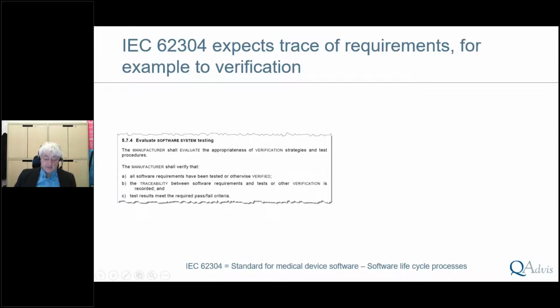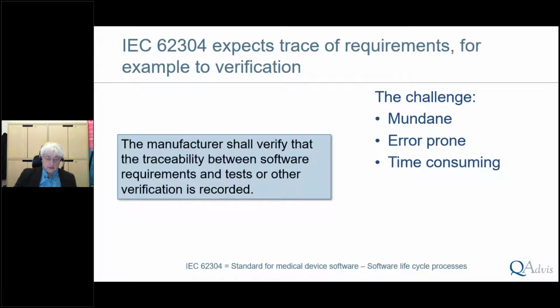The same expectations appear on software level and are elaborated on in the standard IEC 62304, of which you now see a screenshot. If we simplify the standard's text a little bit, it says the manufacturer shall verify that the traceability between software requirements and tests or other verification is recorded. It is mundane and error-prone work to keep this information up to date, not to mention the time spent on the editing, reviewing, and reporting efforts. There is usually a need for different kinds of traceability matrices depending on what is reviewed. Automated document generation with dedicated tools can really save a lot of effort here.